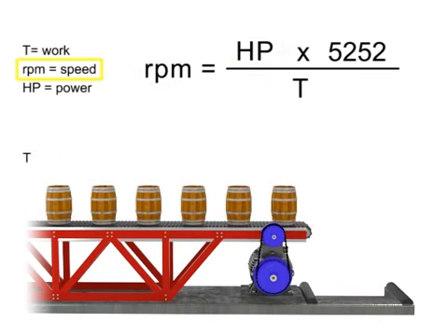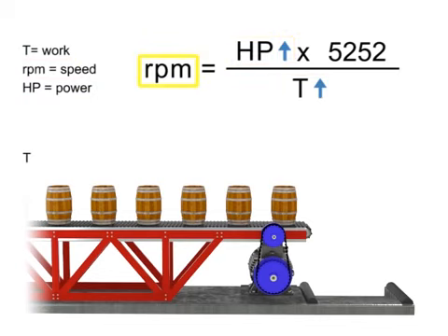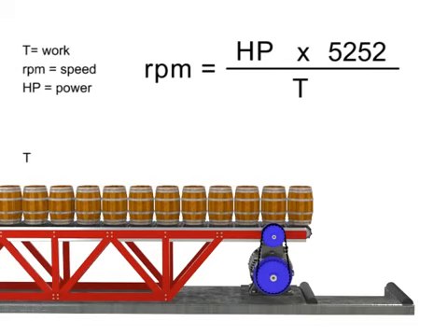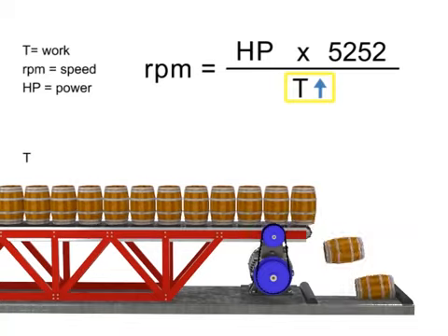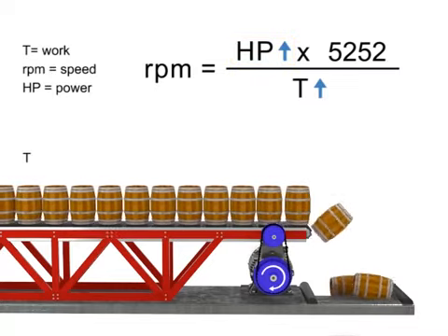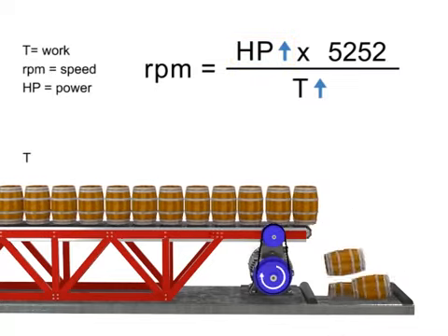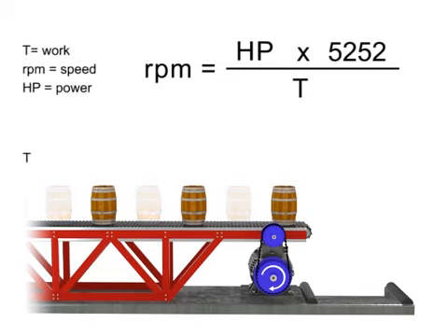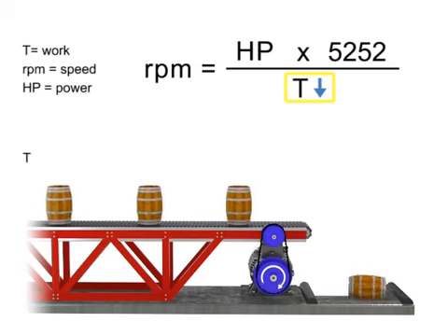If speed remains constant, then torque and horsepower are proportional. As the torque increases, horsepower also increases to maintain constant speed. Let's say we want production to increase, but the speed of the conveyor to remain constant. If torque increases, horsepower also increases to compensate. This means a more powerful motor is needed to produce more torque at the same speed. Similarly, if we wish speed to remain constant and decrease torque, then horsepower also decreases.